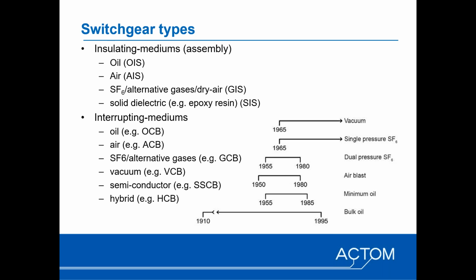and that's solid dielectric insulated switchgear, or SIS. And an example of the type of dielectric or insulating medium is epoxy resin, but there are others. So that refers to the insulating medium within a switchgear assembly that typically insulates the live primary circuit conductors. Then, of course, you get the interrupting mediums, so related to the switching device of the switchgear, whether it's a circuit breaker, a load break switch, switch disconnector, and so on.